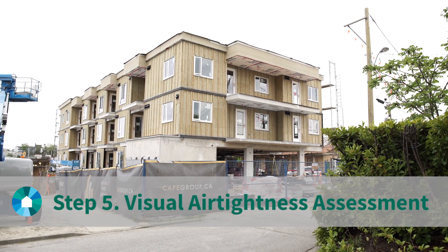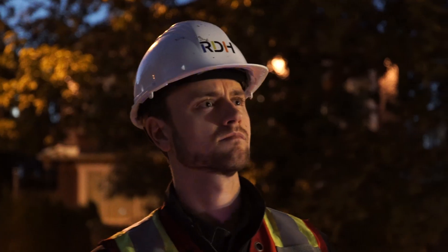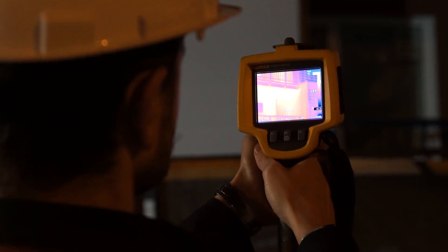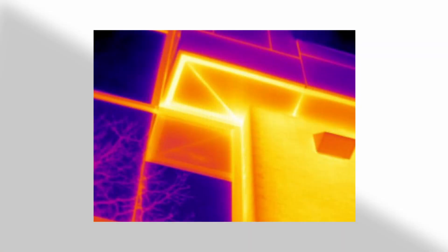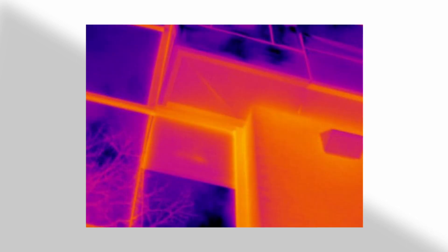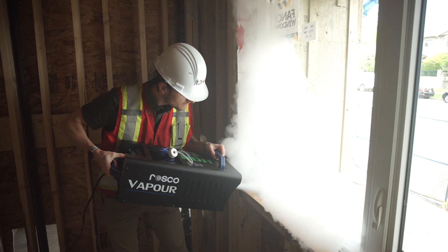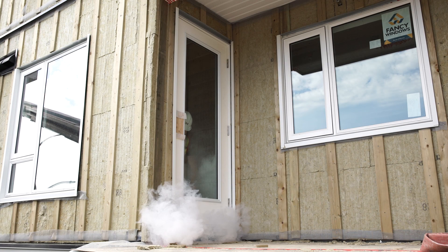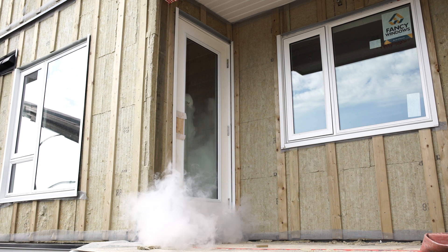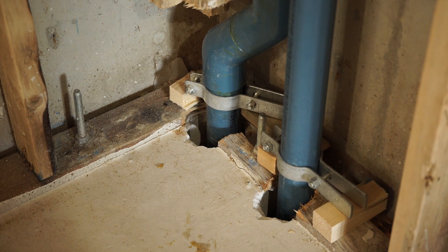A visual assessment is needed to identify the location and magnitude of air leaks. With infrared thermography, warm building surfaces appear as bright spots, called thermal anomalies, on the IR camera. In cooler weather with the building heated and pressurized, thermal anomalies from air leakage locations show up during a scan of the outside of the building. A second scan is then done while the building is depressurized and the air leakage locations are cooled back down. Smoke tracer testing is typically completed using theatrical fog applied to the interior of the building while pressurized, and air leakage then appears on the exterior when it leaks through the enclosure. Smoke tracer testing can also be done from the outside with the building depressurized. This testing is best performed with the mid-construction air tightness test when the air barrier can be more easily accessed and repaired if needed.